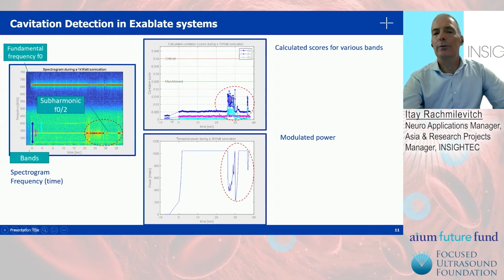What you can see here is that from the beginning of the sonication, this is ramping up and then the sonication started. You can see that there was no cavitation and at a certain moment the cavitation was going up. And the score was telling that. Once the cavitation was going up, we decreased the power automatically in order to cause the cavitation to relax, which indeed happened. Once it was relaxed, the power was automatically going up and the cavitation was not there for a short while, then jumped again and went down.